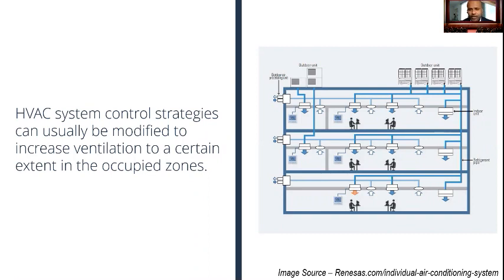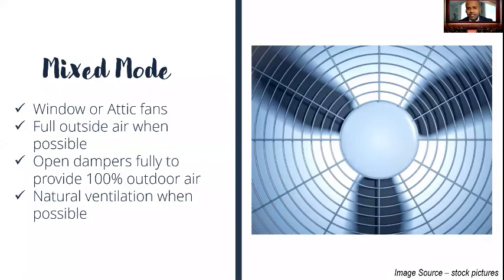However, this is not a simple flick of a switch, as HVAC systems are complex and usually designed for individual buildings within standard specifications. Spaces where the air conditioning system normally runs in recirculation mode may be set up to run on full outside air when possible. In many cases where dampers are not fully open, when weather permits, make sure to open the damper fully. One thing to note here is if you have a building automation system or a BMS, you may have to make sure the dampers are fully open. In many cases, the BMS will tell you one thing and the reality will be different.